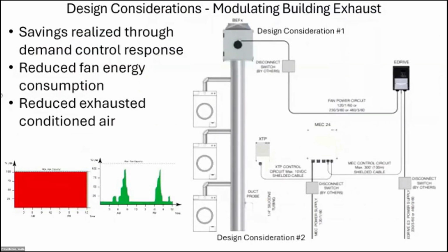So we're going to start things off. This is actually a case study that we did with Enbridge Gas and the Natural Gas Technology Center here in Canada. So this was a large multifamily application that had an existing constant speed exhaust system for their central laundry, all right? So each floor is stacked on top of each other. This was a 3-story building, and each one of the domiciles was basically a mirror of the one below it. So each one of the appliances is pulled over to a central trunk line, and all of the exhaust is performed by a central fan located on the roof.